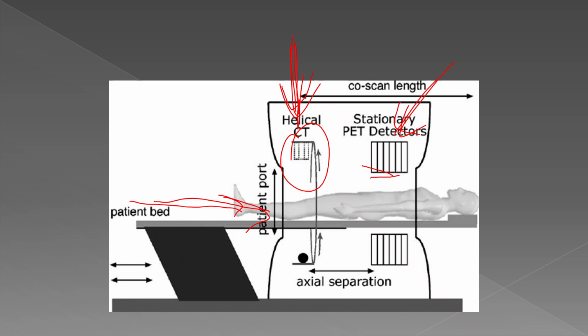It's data that's extracted from the CT map that then gets applied to the PET images when the PET images are reconstructed. And so the CT is performed first, and then the PET study, the CT gets applied for iterative reconstruction purposes and things like that to the PET images. Now, most of the time, the patient will get their CT first.